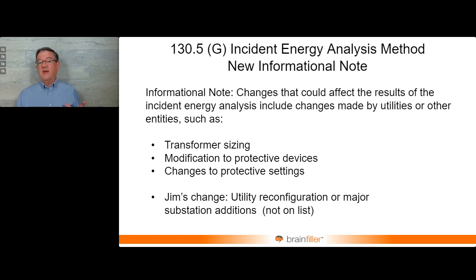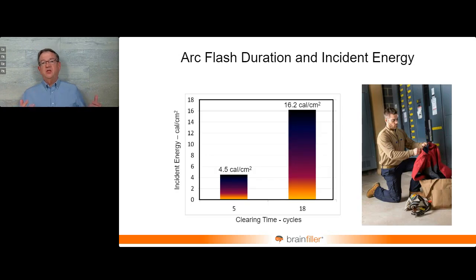And short circuit current is a key component to how severe the arc flash can be. Now, on the issue of what could affect the results of the study, I look at this as: does it affect the PPE? So if you have PPE specified for a given area of, let's say, 8 calories per square centimeter, and your study says it's well below that, like 4.5 calories, and somebody reviews the study and it goes to 4.8, 4.6, something like that, at the end of the day, so what? 8-calorie PPE still works. But if there's a change that pushes that well above, that's a problem. And you need to go back and reevaluate what needs to be done there.